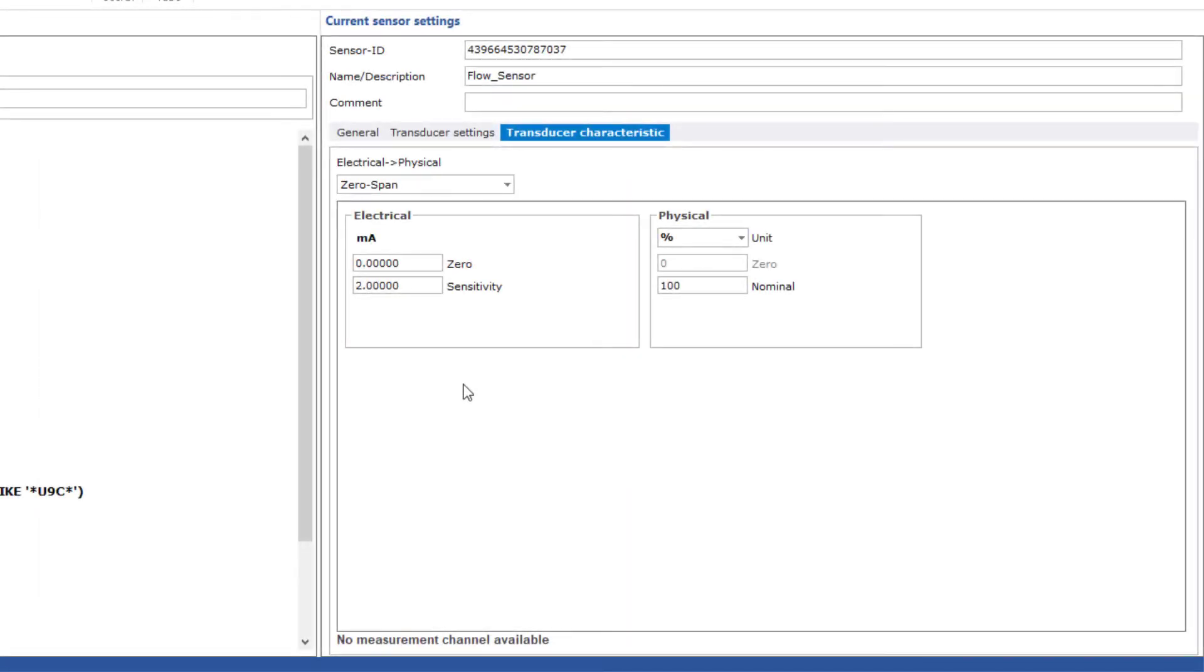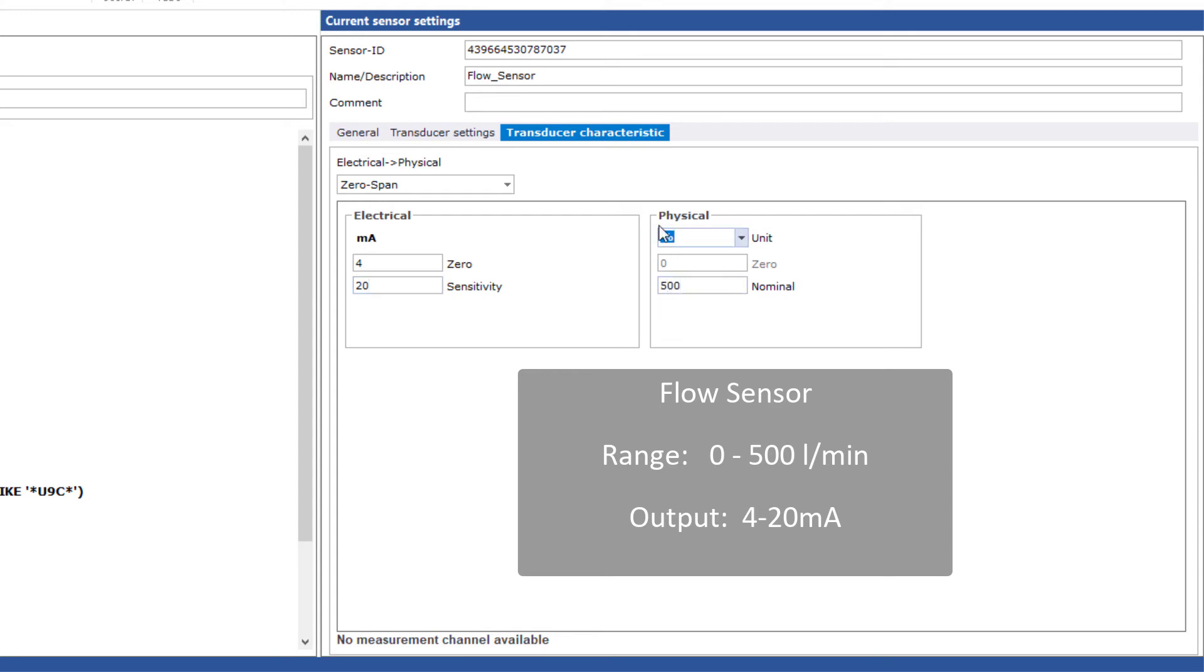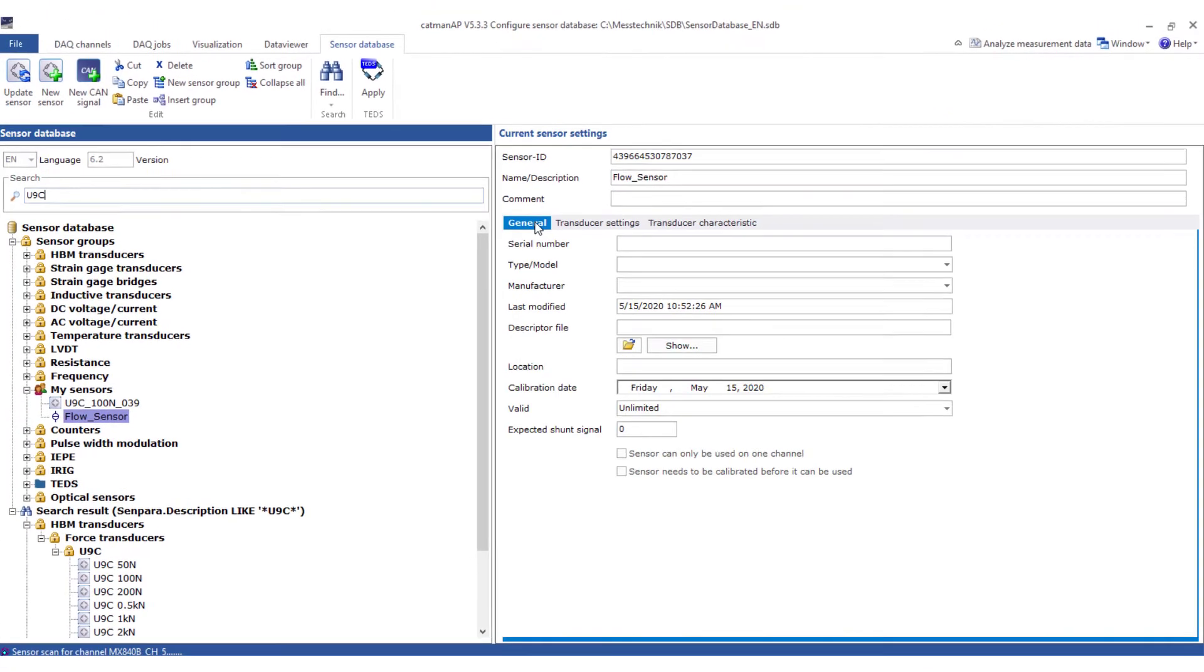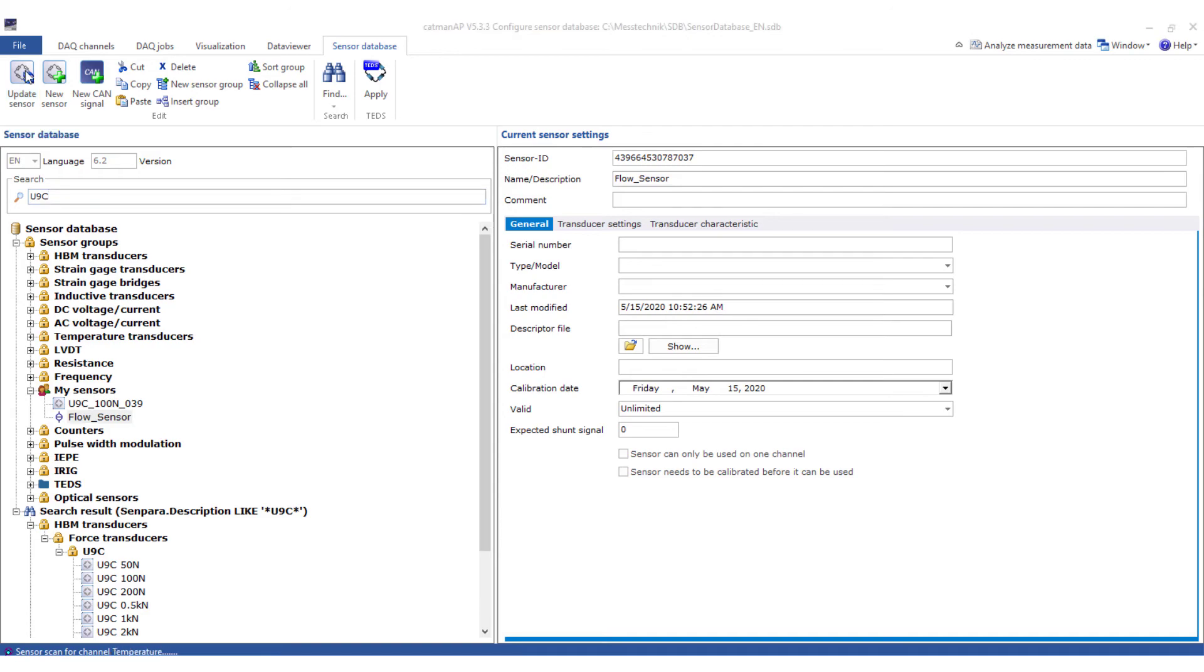Back to my flow sensor. Here I select zero-point span and enter the required parameters. Four milliamps correspond to zero liters a minute and 20 milliamps correspond to 500 liters a minute. Under General, you can enter additional parameters. Finally, click Update Sensor. Done!